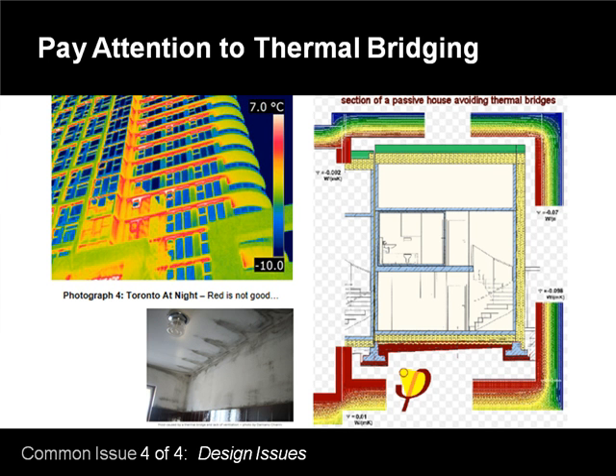I thought these pictures were very telling, particularly the one on the top left, which was an infrared thermography scan. As designers, you design a building and assume you have R19 insulation, R28 insulation. It might say that on the data sheet, it might look that way in a simple model. You go out and look at how the building's constructed, and that's what you're actually seeing. The amount of thermal bridging that we see on jobs is absolutely enormous at parapets, slab edges, balconies, you name it, from a design standpoint.